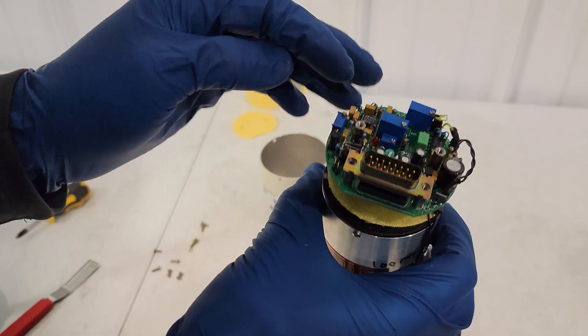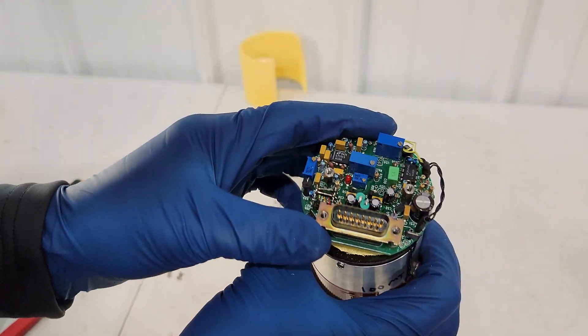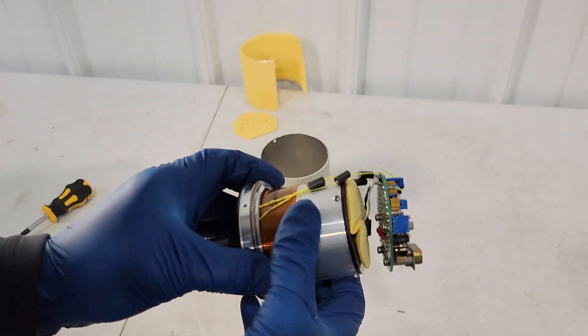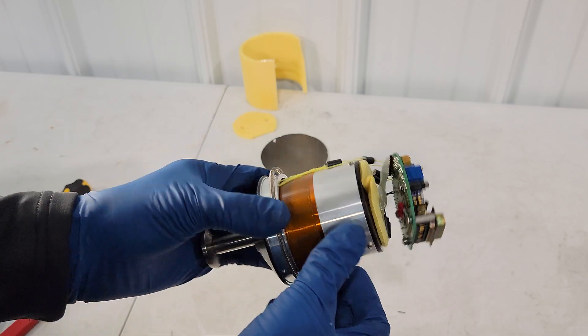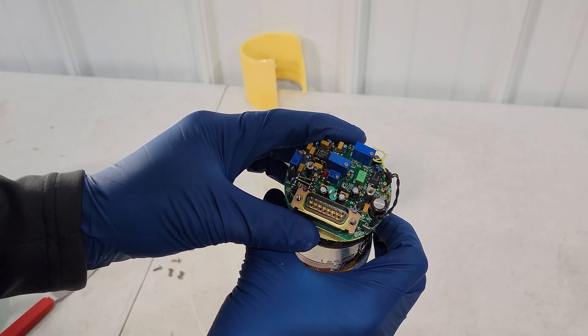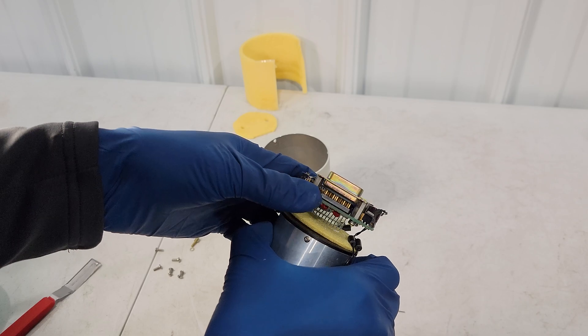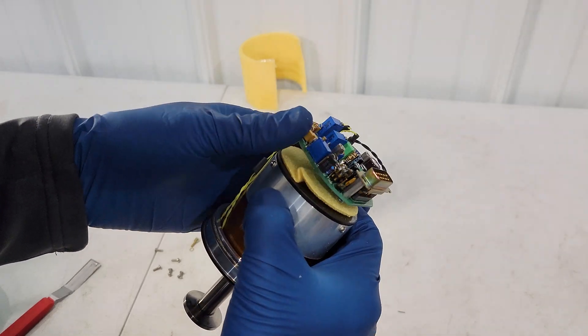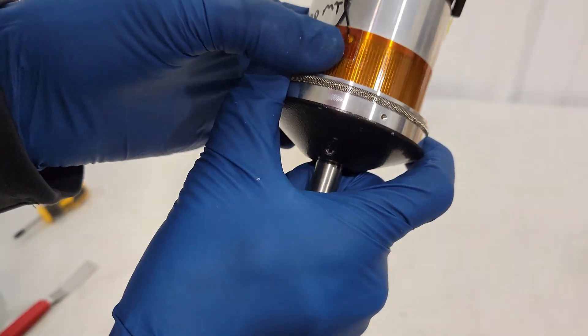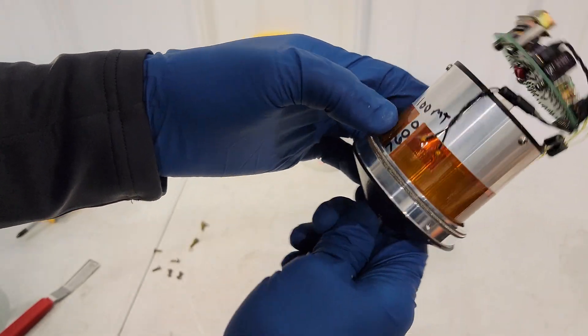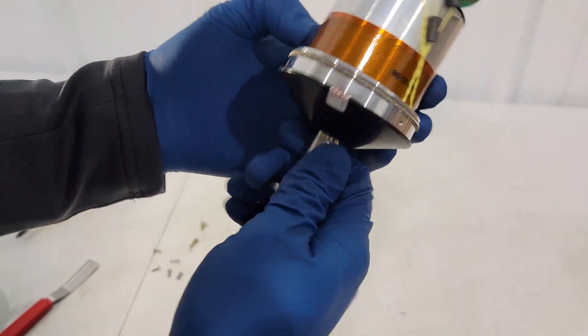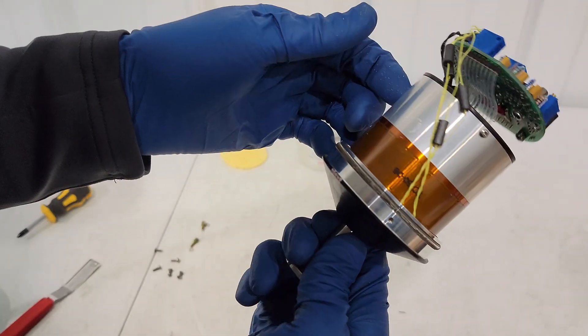So a couple of chips as well as some potentiometers for adjusting the zero point, the span, probably some other voltages as well on the control board itself. So this, as with any capacitance manometer, is actually not a sensor but a transducer. Meaning that it doesn't just output the raw signal that it has inside of it, it actually has an active circuit board that is giving you the signal output. I think this is a heating element on the outside, some sort of resistive heating pad that's placed around the outside of the whole transducer.